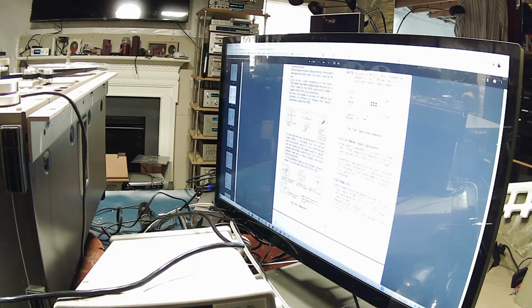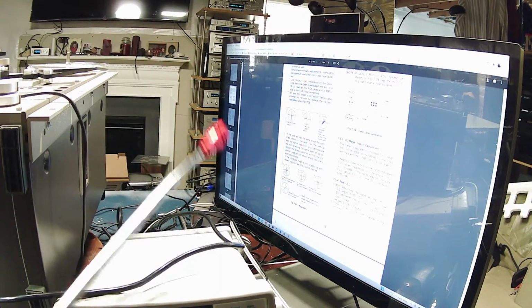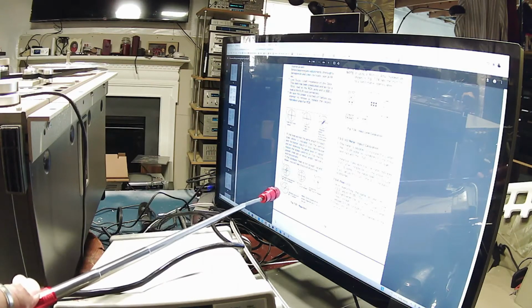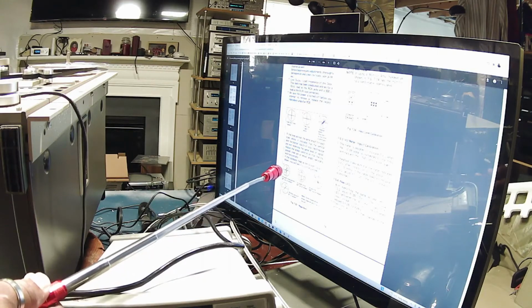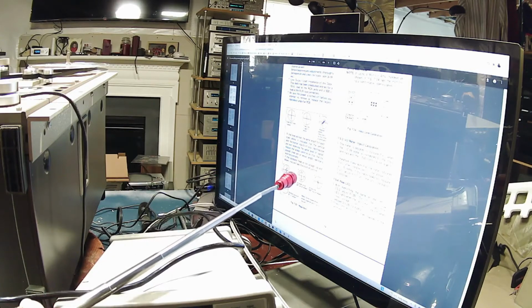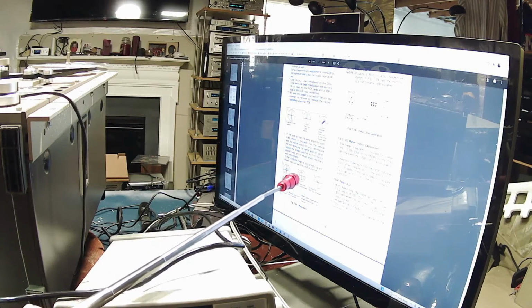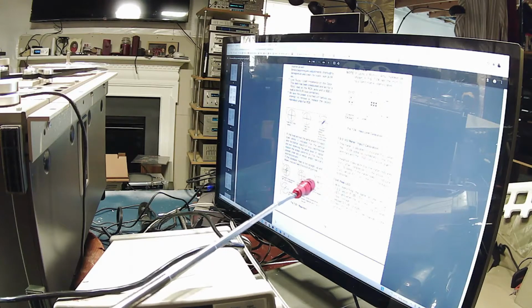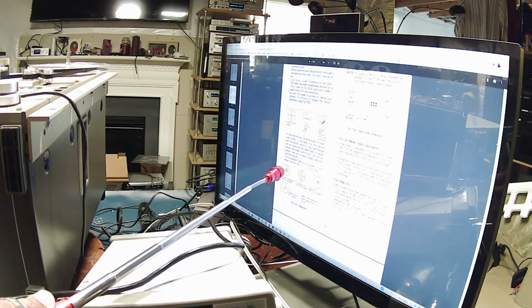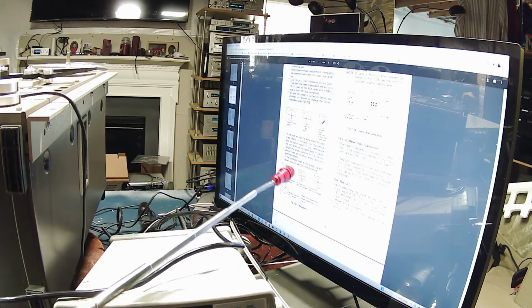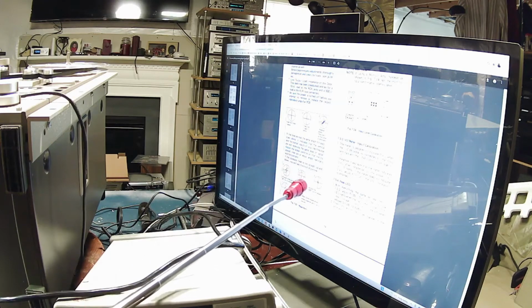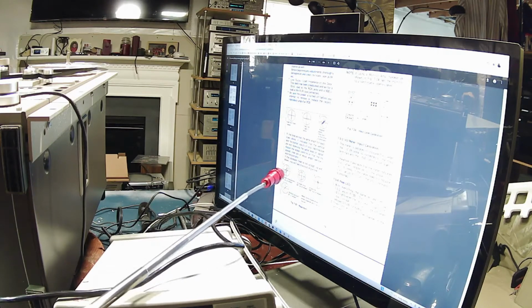For this portion of the calibration, we're going to do the head alignment check. I've already adjusted the heads. This is a perfect alignment. This is acceptable. When it gets up to here, it's acceptable also because it's 90 degrees out of phase. But if it goes this far, or this oblong signal is tilted to the left instead of to the right, that means it's past 90 degrees out of phase.